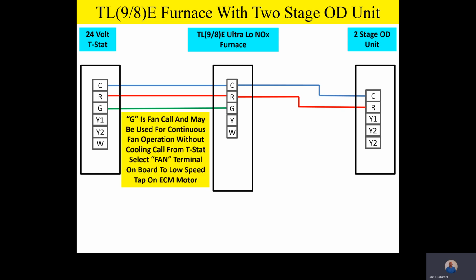Now, as we start taking a look at our fan call, it should be noted G is our fan call, and it may be used for continuous fan operation without a cooling call from the thermostat. So remember, team, if the homeowner goes over to the thermostat subbase assembly and goes from auto to on on the fan, it's going to generate a 24-volt signal on the G terminal. That fan call can be used as continuous fan operation without a cooling call from the thermostat. This is a very nice feature on our Champion control board that allows us to circulate air at a very low RPM or a low motor speed. It allows wonderful filtration across the clean air devices, electronic air cleaners, media air cleaners. And a lot of homeowners like to do that.